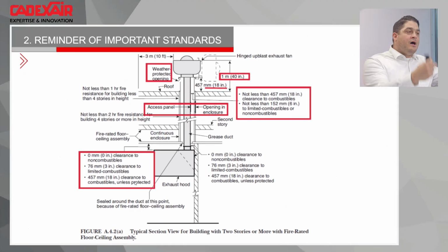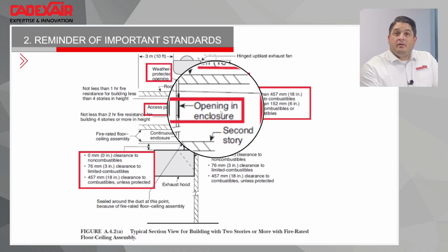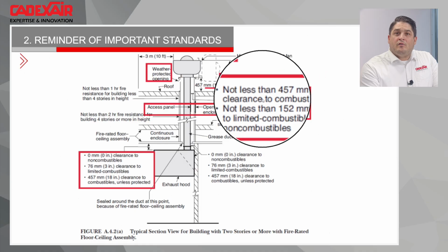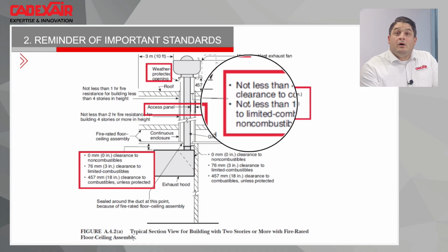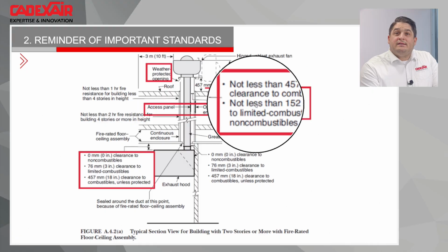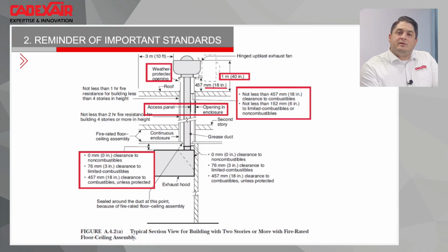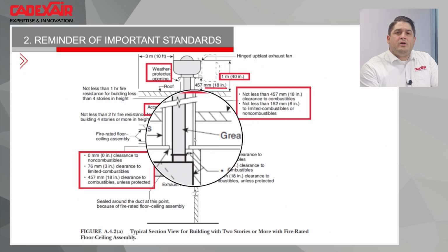So if the hood is on a wooden stud in the back, you have to put an 18-inch spacer, or I will say you need to put special insulation. A lot of manufacturers have listings for that, so they will put insulation wool, and that will be good. But the only place it's different is inside the shaft. If we're going really inside of the shaft, there's a note here: 18 inches of clearance to combustible, nothing new, but it's 6 inches to limited combustible or non-combustible. So they want 6 inches to everything around the ductwork.